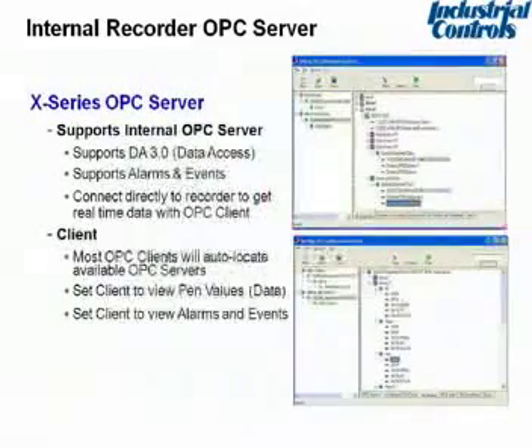There's also something called OPC. There was a time when, in order to interface a PLC or someone's DCS system to a device like a paperless recorder, there had to be code written. Then there was a lot of talk about Modbus TCP/IP, which is available now, but the latest trend is something called OPC, a technique that allows a paperless recorder to talk to a PLC or a DCS on your network without having to go through the vendor's application software like Trend Server Pro.